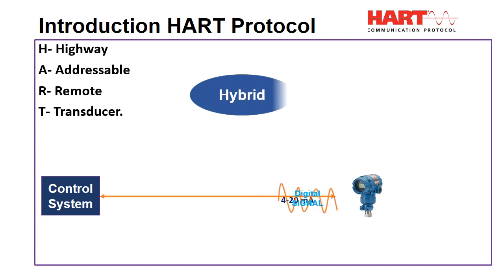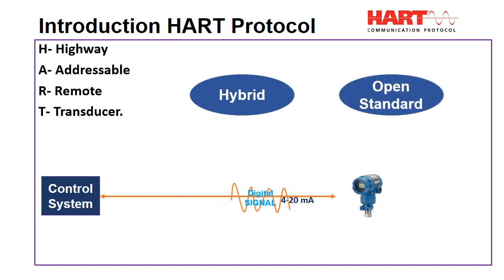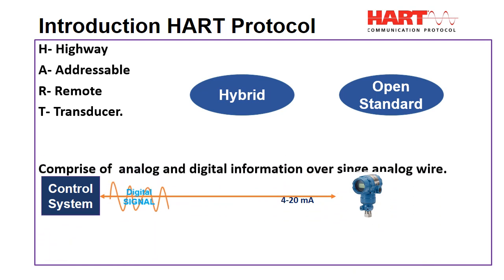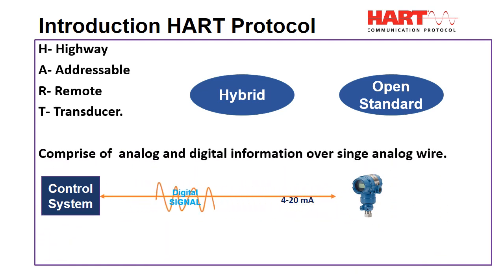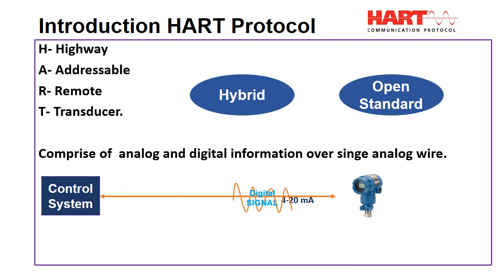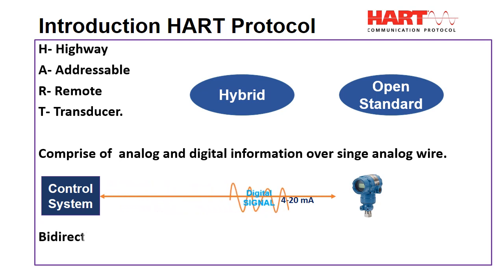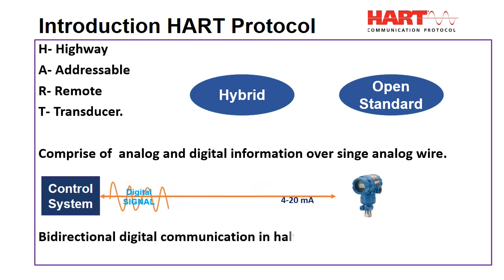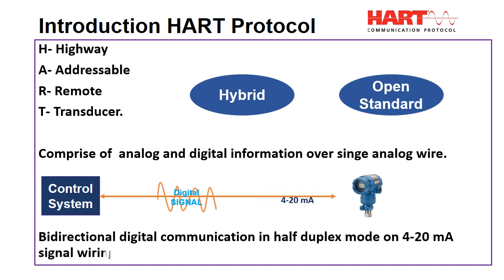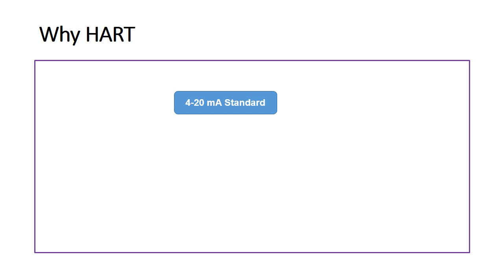HART is a hybrid open standard communication protocol because it comprises both analog and digital information over a single analog wire. HART provides bi-directional digital communication in half duplex mode on 4 to 20 milliampere signal wiring. Most smart devices used worldwide are HART enabled.